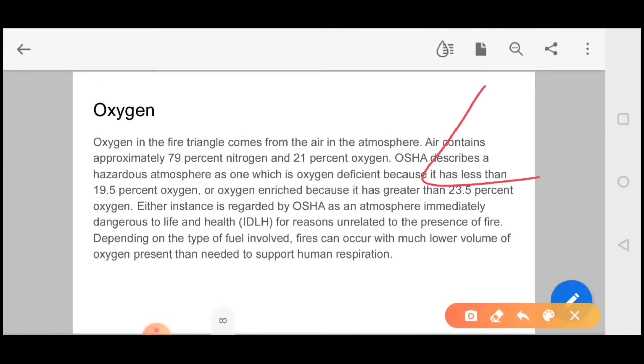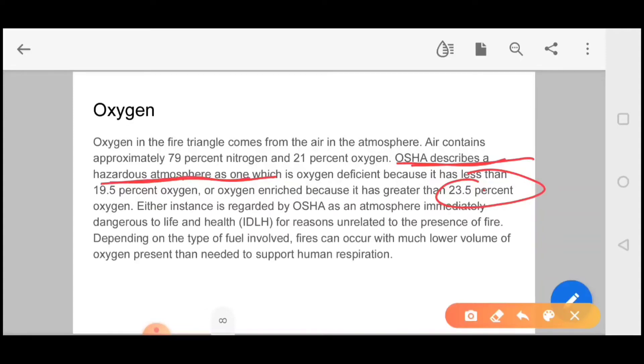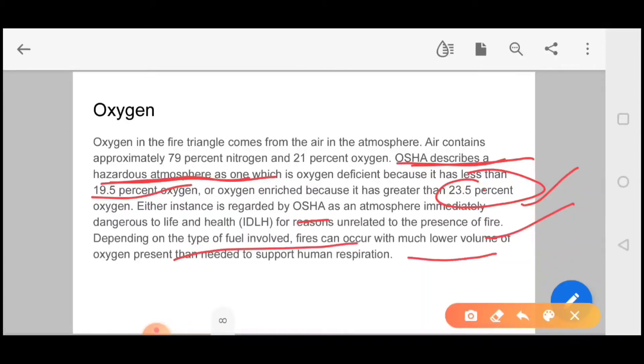Next is oxygen. Oxygen in the environment is normally 21%. If oxygen is less than 19.5%, it will be hazardous. If the atmosphere has more than 23.5%, it will also be hazardous. OSHA describes a hazardous atmosphere as one which is oxygen-deficient (less than 19.5%) or oxygen-enriched (greater than 23.5%). Either condition is regarded by OSHA as an atmosphere immediately dangerous to life and health.